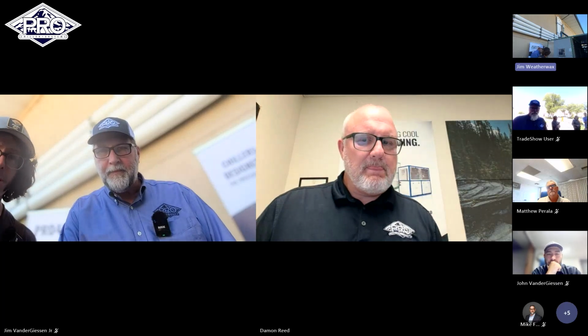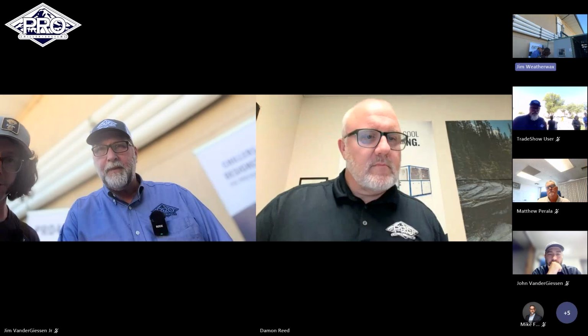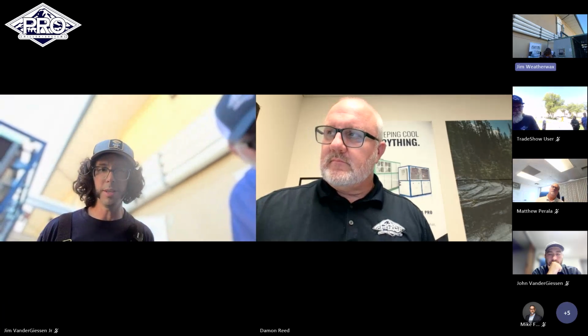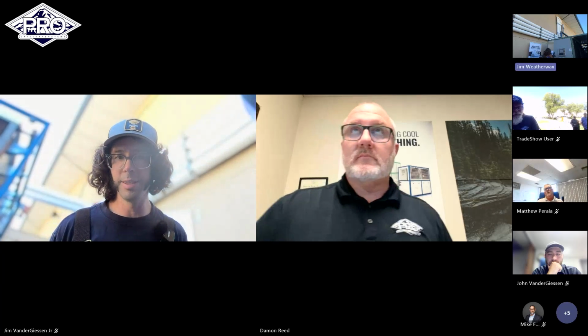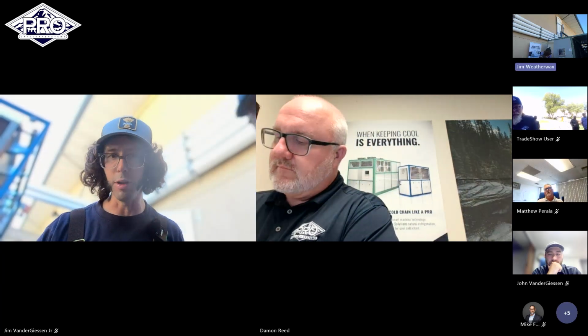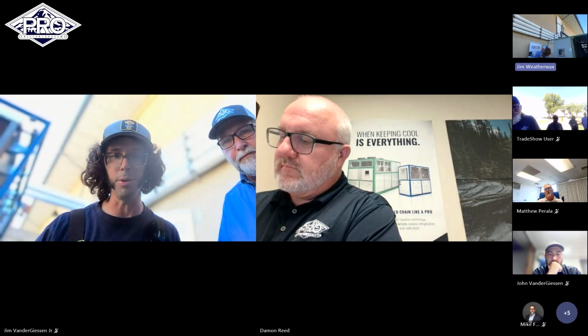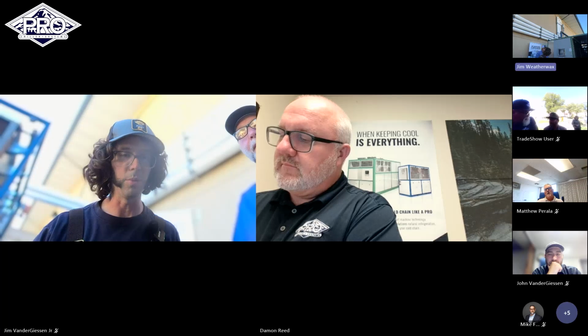You got any questions, Nick? Well, we're going to be doing some trials in the next couple of weeks, going into another big brewing cycle, and spending a little more time on the heat recovery part would be interesting to us. Like we were talking about before, it'd be good to brainstorm some way to control the outlet temperature of that potable water HX, so that we can modulate the flow through that heat exchanger to maintain a set point on the hot water outlet when we're running, and automate that.